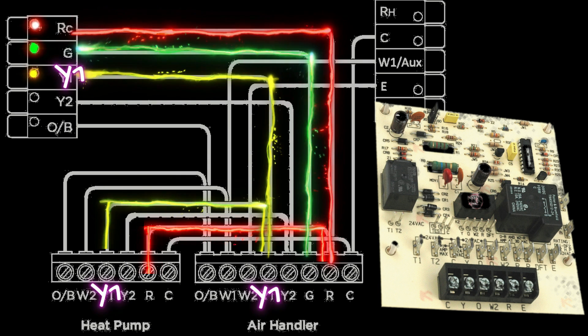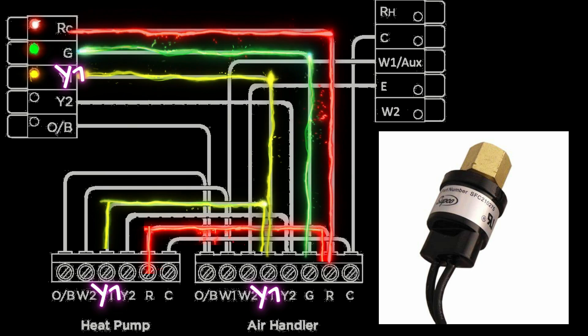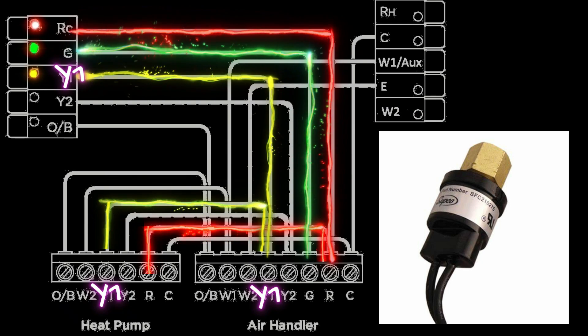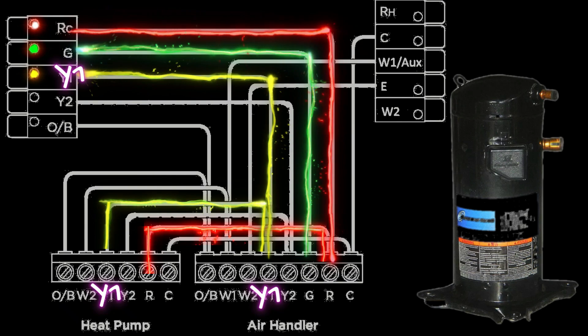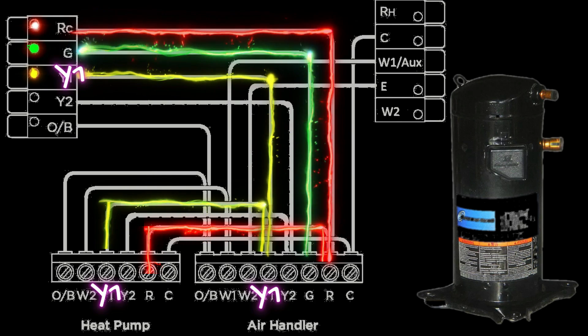Now this signal is going to go through a couple of pressure switches, high and low pressure, to prevent the compressor from powering up if we have abnormally high or low pressures in our refrigerant in the system, so it protects the compressor.